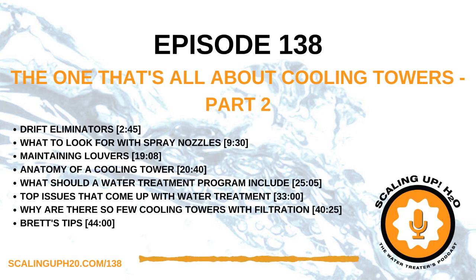Sometimes those louvers get so covered with evaporative salts and organic material—how much can build up before it starts disturbing how much air is actually going into the cooling tower? You need airflow through there to cool the water flowing down through the fill. These open cooling towers are giant air scrubbers, scrubbing whatever's in that air, and a lot of it gets deposited on those louvers. So there should be some type of maintenance program, either power washing them off, or another thing I've seen people do is keep extra louvers on hand.